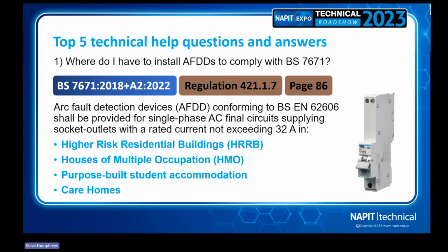So what it does say in the regs as well is, common sense would say, if you're doing consumer unit replacements, you'd need to include AFDDs with any sockets below 32 amps in these particular areas. And you can see where this reg came from, because originally this was quite a long regulation, more or less all situations, but this was cut down to just these areas where it's probably more safety critical.